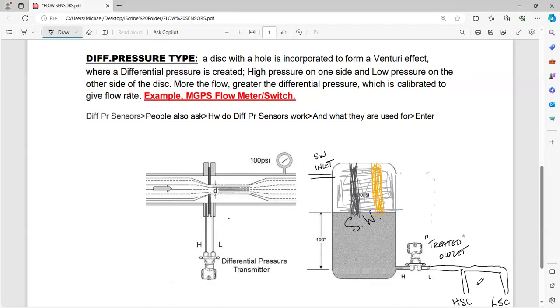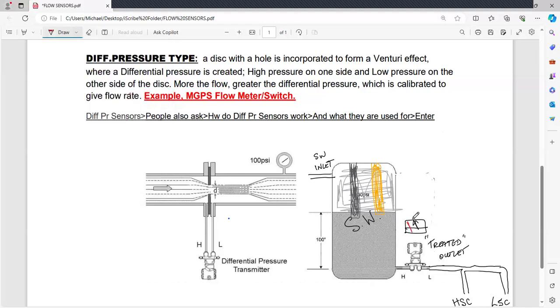Okay. So how does one know how much water is going? If you remember, I said there is a flow meter to give you this indication. If that water is insufficient, that means there is going to be a meter attached over here. Okay. And generally, it's going to have a black needle as well as a red needle. If anybody has sailed with this type of thing, this needle is going to be showing how much of that flow is there. The red needle is a set point.